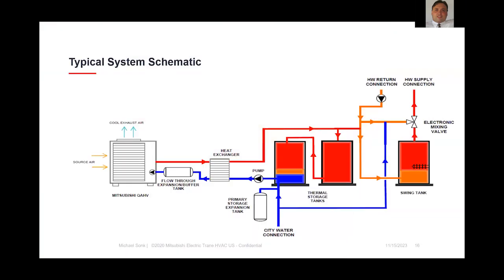All right, so we're going to get into more of the details and specifics of the componentry, application, and sizing considerations. First off, we'll start at a 10,000 foot level, looking at the major components of these systems. This is just a typical schematic, pretty representative of heat pump CO2 based domestic hot water heating systems. This may vary slightly from manufacturer, but I think you'll find this fairly common in terms of application. This is obviously based on the Mitsubishi QAHV product, being an air source, outdoor located CO2 heat pump water heater.